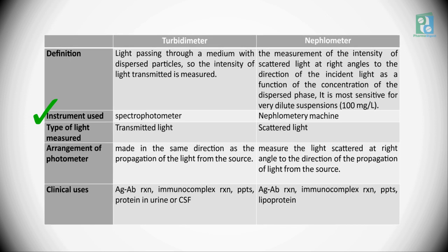Another difference is the type of light which is measured. In a turbidometer, it is transmitted light, and in a nephelometer it is scattered light. The difference regarding the arrangement of the photometer: in the case of a turbidometer, it is placed in the same direction as the propagation of light from the source. In a nephelometer, it measures the light scatter at a right angle to the direction of propagation of light from the source.